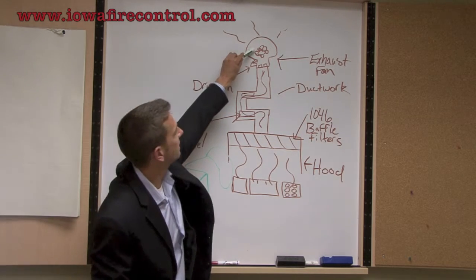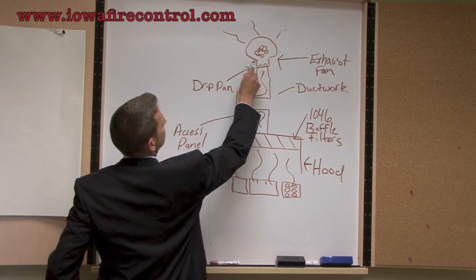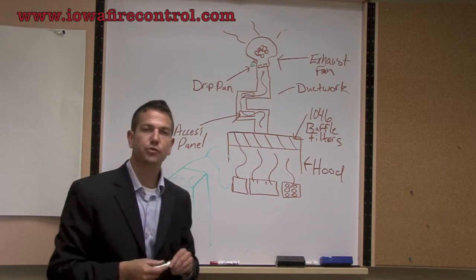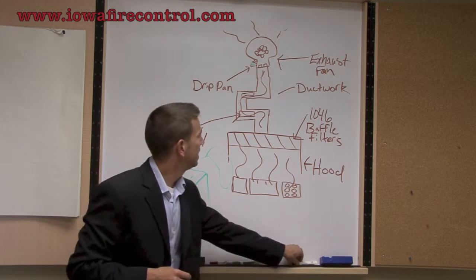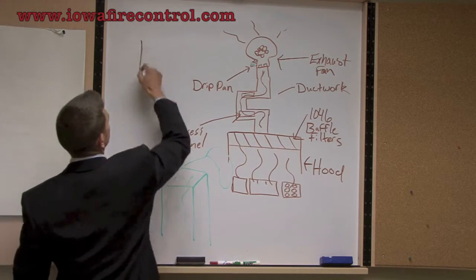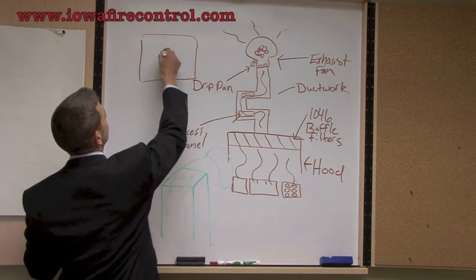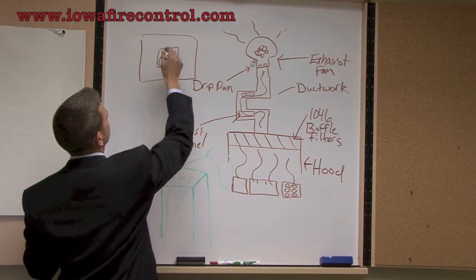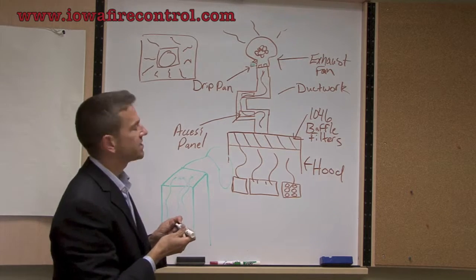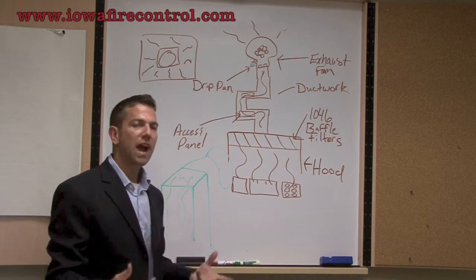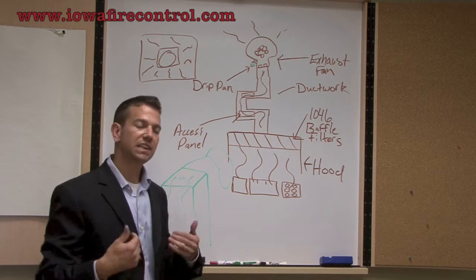The exhaust fan sits up here on a hinge kit, and there's also a drip pan, drip box, or some kind of grease containment system. Many times on different roofs we find what they call a sandbox. It's a large box — this would be an overhead view — and the fan sits here with the ductwork here. Grease goes all over the place inside this box, and they call it a cat box or sandbox because usually there's some type of gravel or material like a spag that absorbs the grease and lets the moisture pass through.